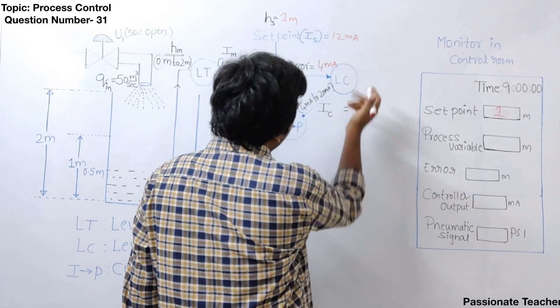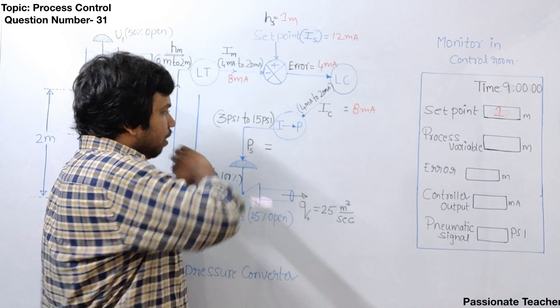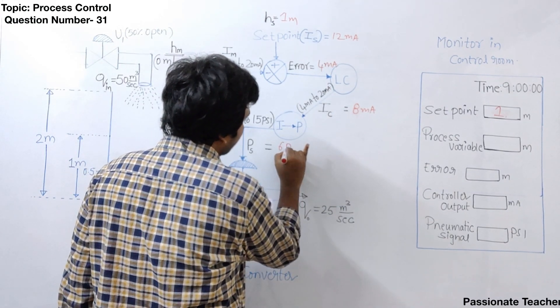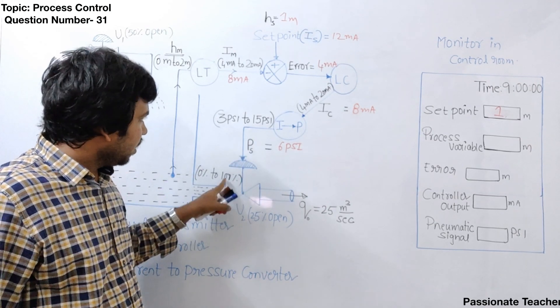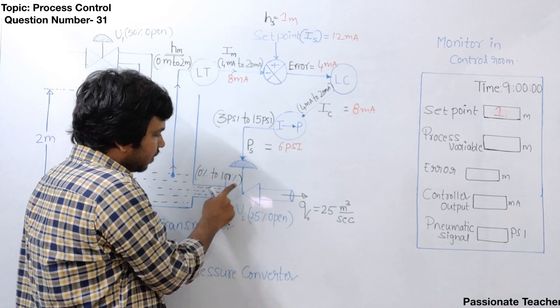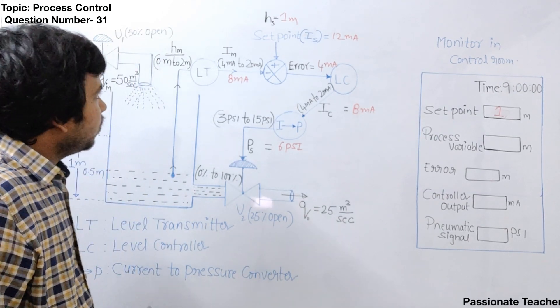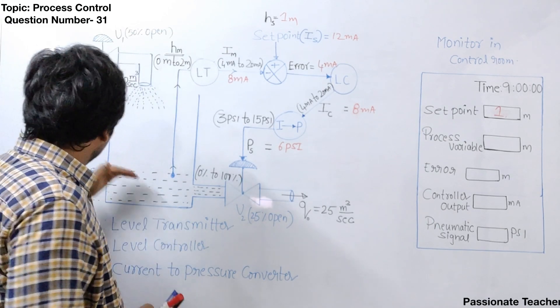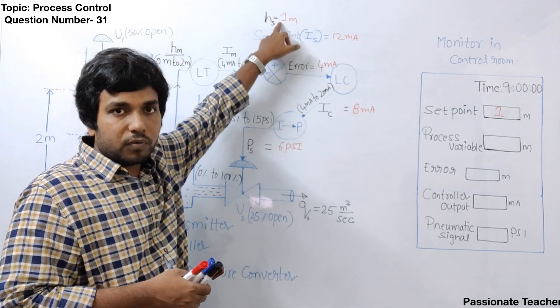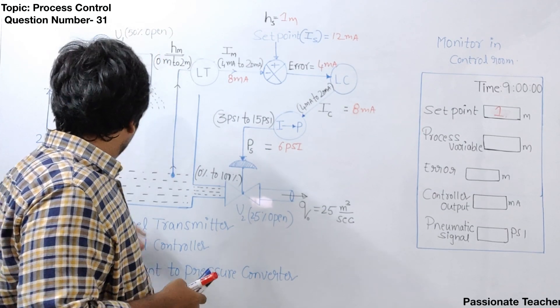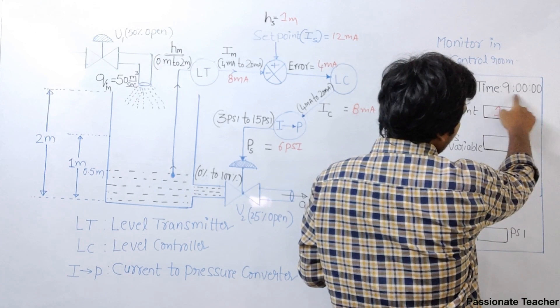With the error signal of 4 mA, let's consider the controller is generating 8 milliampere current. When it generates 8 mA, the I2P converter produces 6 psi pressure. Since 3 psi corresponds to 0% and 15 psi corresponds to 100%, a 6 psi pneumatic signal means the valve is at 25% open, giving an output flow rate of 25 cubic meters per second. We want the water level at 1 meter, but there is still an error — the current water level and the required level are not the same.